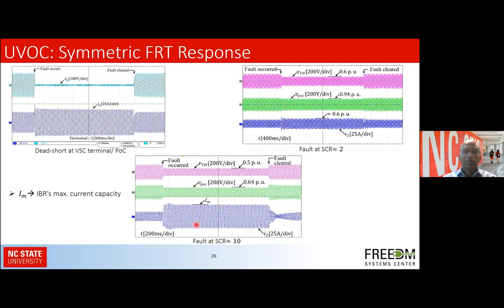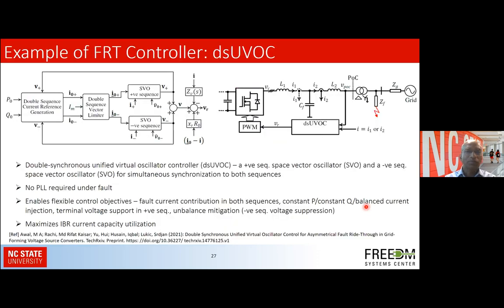operation, maintaining within the maximum limit of the converter capacity. So this Imax is the limit, and it has not been exceeded. Then the double synchronous reference frame has been used for riding through asymmetric faults. So here again, we have a double synchronous vector limiter that goes into this space vector oscillator and then generates the positive sequence and the negative sequence commands for the converter. A fault is simulated over here.